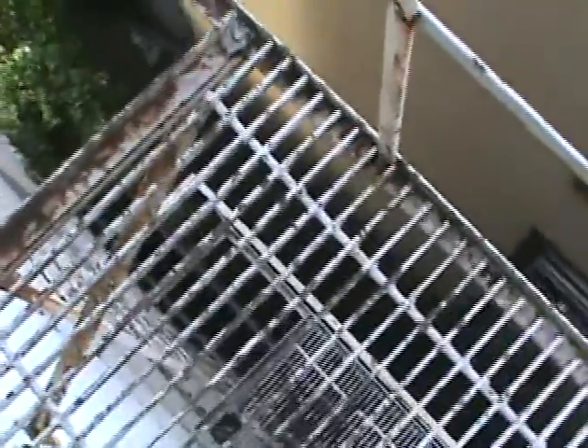The authority having jurisdiction shall accept by load test or other evidence of strength. That is the NFPA code. The fire code states that depending on the structural condition, a load test may be ordered. This fire escape definitely has structural problems, as you can see. And number three, the International Building Code states that a fire escape must be examined, which is what we're doing right now, and can be load tested, or it can be certified.